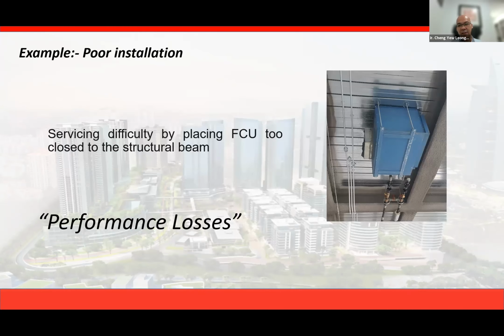And this picture shows an FCU located very close to the structural beam. What happens is you have a return air problem - this is the first issue. Second is you have a maintenance issue - how are you going to remove the filter from the FCU? For those unsure, normally the FCU's filter is placed at the back, this is the return air as shown by my cursor. So all these are performance losses, right?